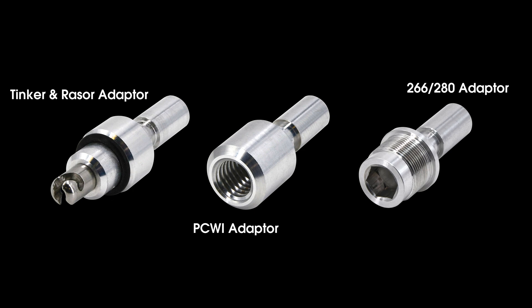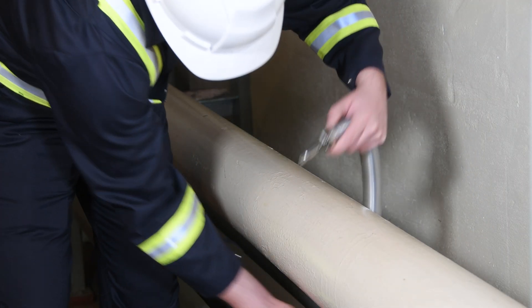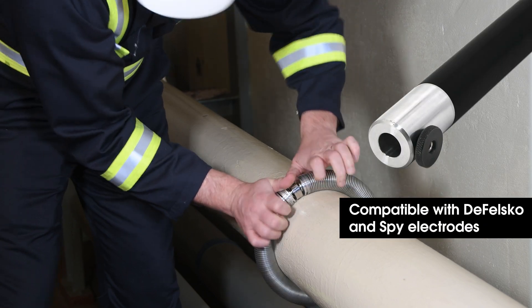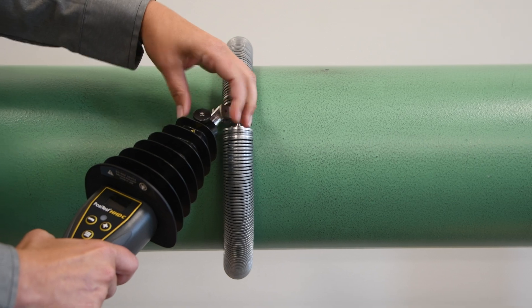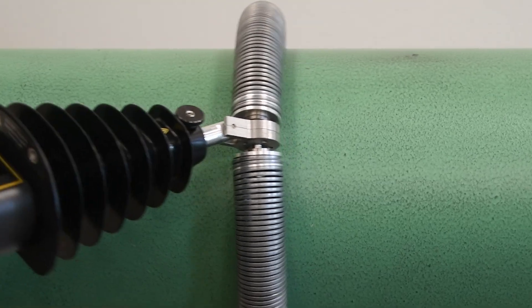Adapters for all major competitive electrodes are available for connecting existing spring and brush electrodes from nearly any brand of holiday detector. The PosiTest HHD series is directly compatible with DeFelsko and SPI electrodes. To attach the desired electrode, simply use the knurled thumb screw to secure.